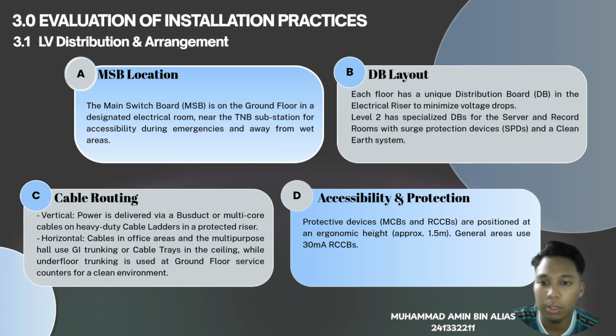Then DB layout, distribution box layout. Each floor has a unique distribution box in the electrical risers to minimize voltage drop. This arrangement ensures the shortest possible length of final subcircuits, so it will reduce the voltage drops throughout the system.